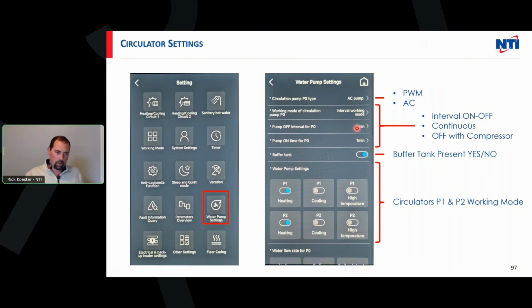Pump off intervals, again, if I'm using interval mode, here I can select whether or not I'm using a buffer tank. I mentioned before, if I'm not using a buffer tank because my system volume exceeds what my minimum is for that application, well, then I'm going to turn that off, but I'm going to take my buffer tank sensor and strap that to the return side coming out of my buffer tank going back to the outdoor unit, and we'll monitor our temperatures from there.